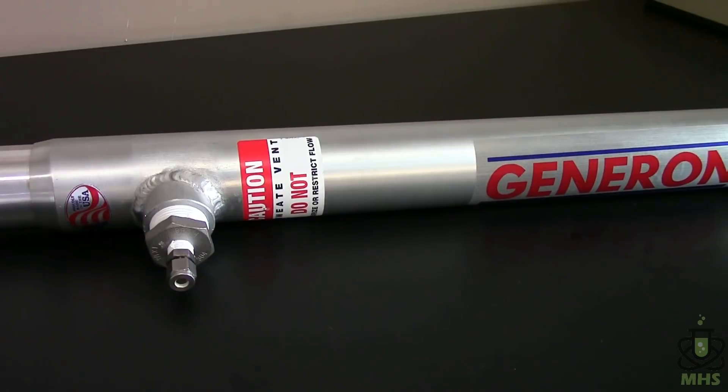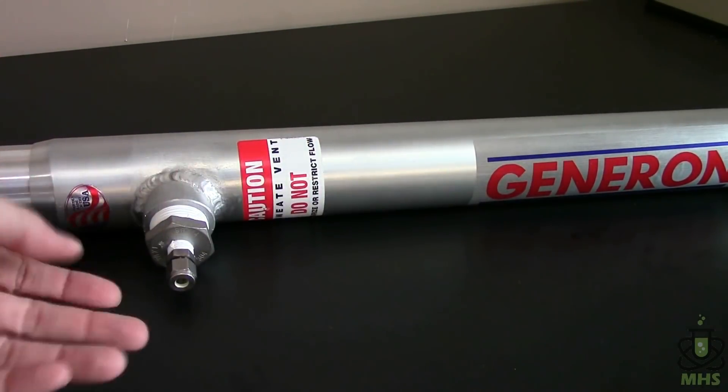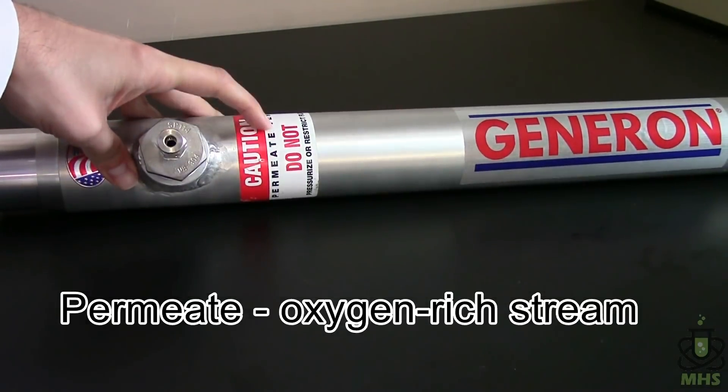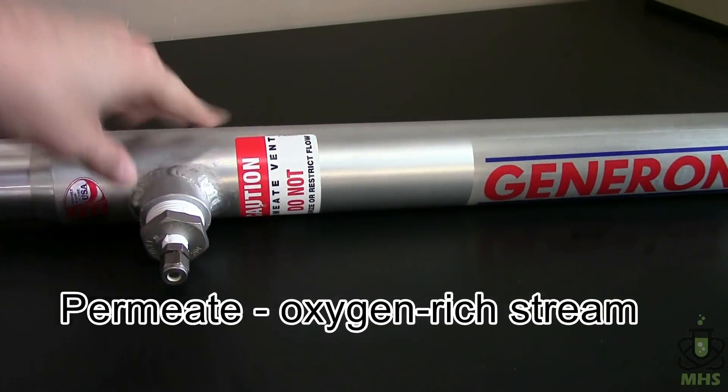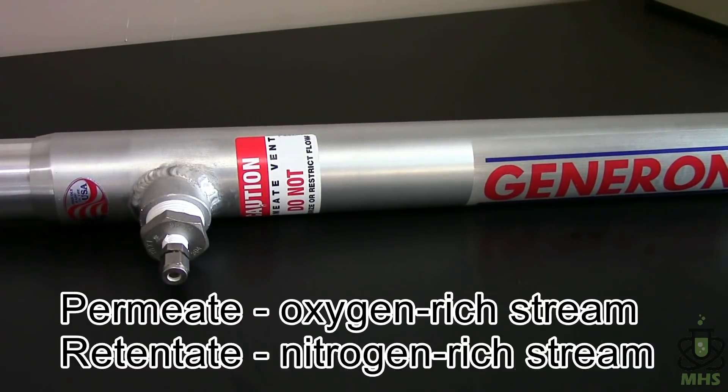The two streams of gases that this separates the air into have two different names. The stream that permeates through the fibers and comes out this sidewall here is called the permeate stream. And you can see it's written on here this is the permeate vent. The other stream that continues on through it that is retained inside the fibers is called the retentate stream and that's going to be your purified nitrogen gas that comes out the other end.